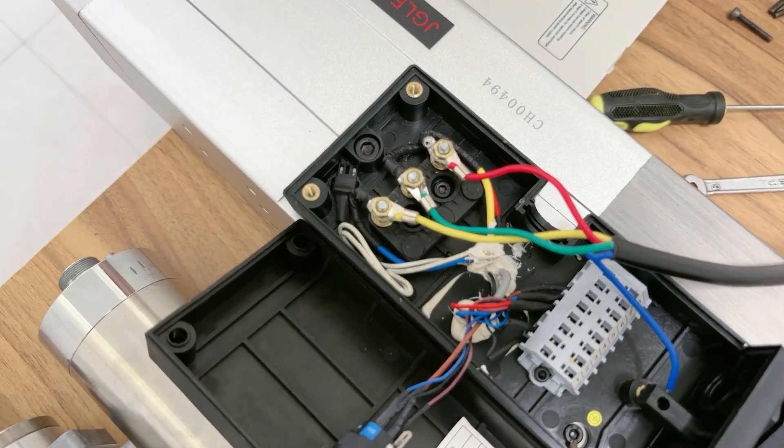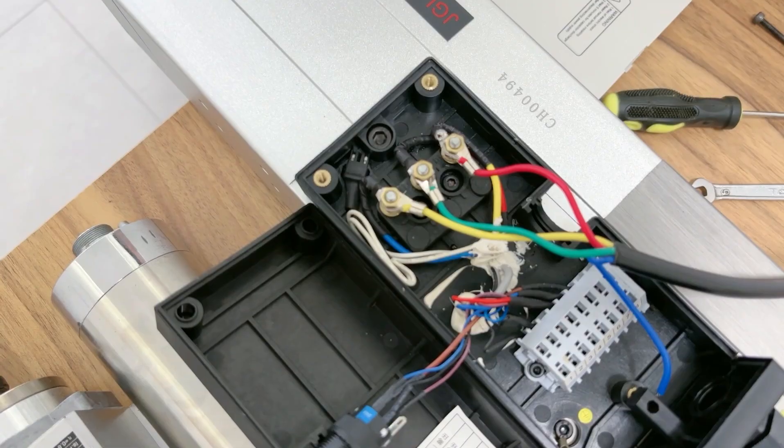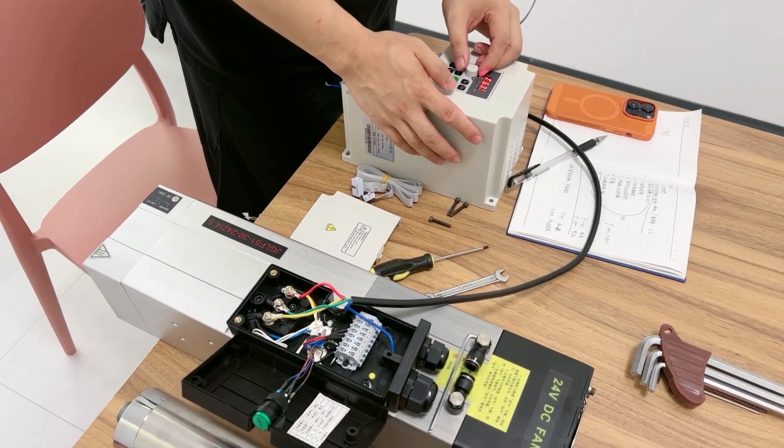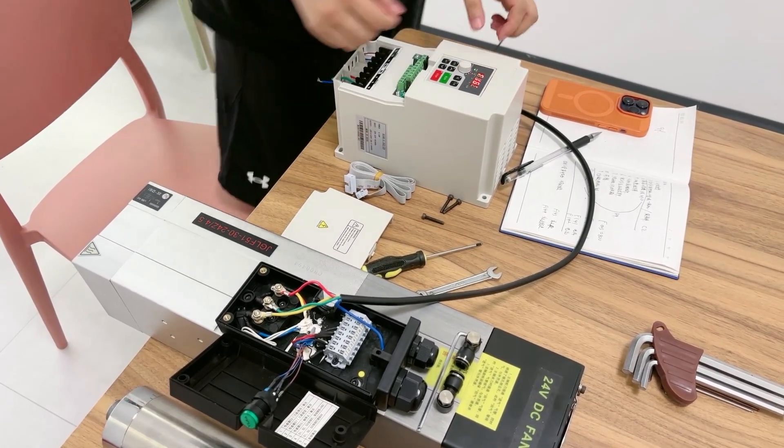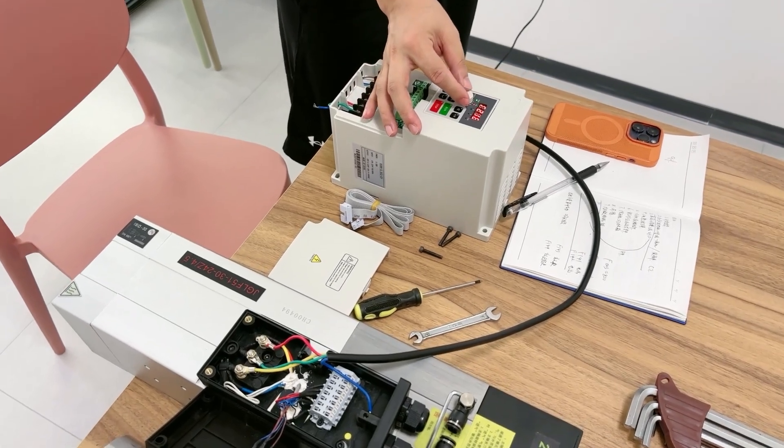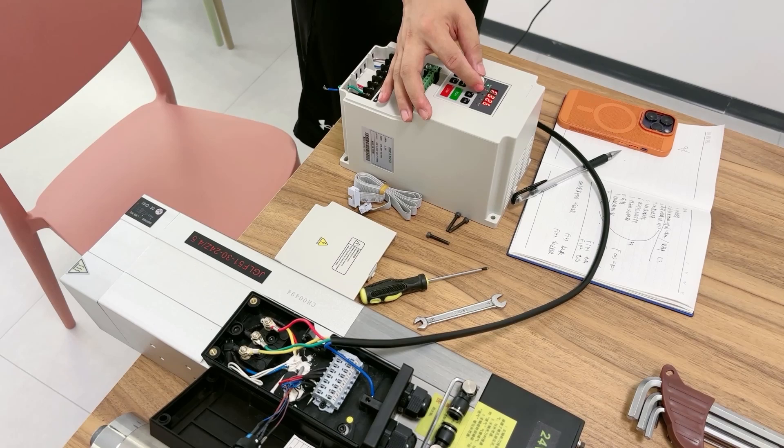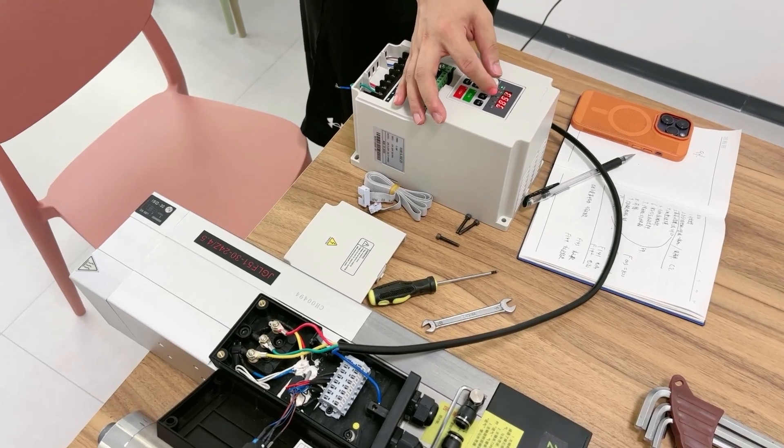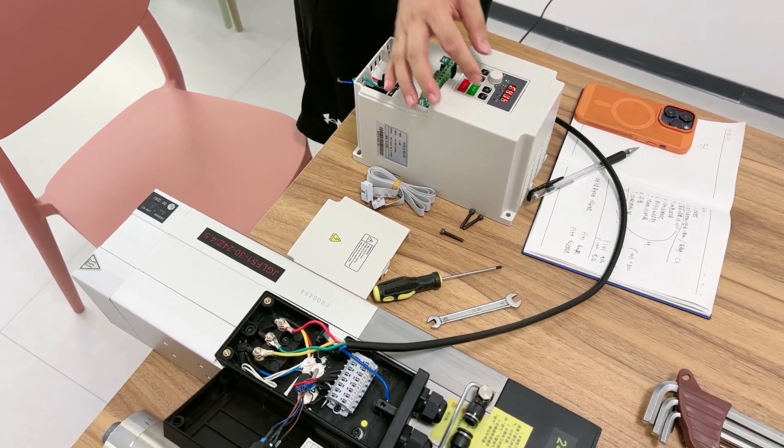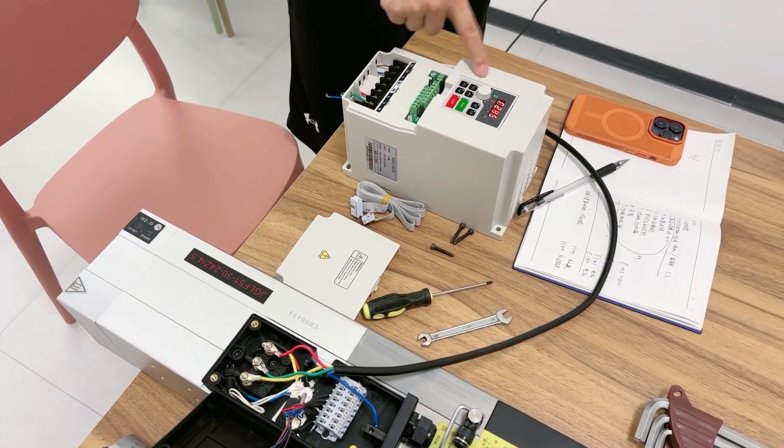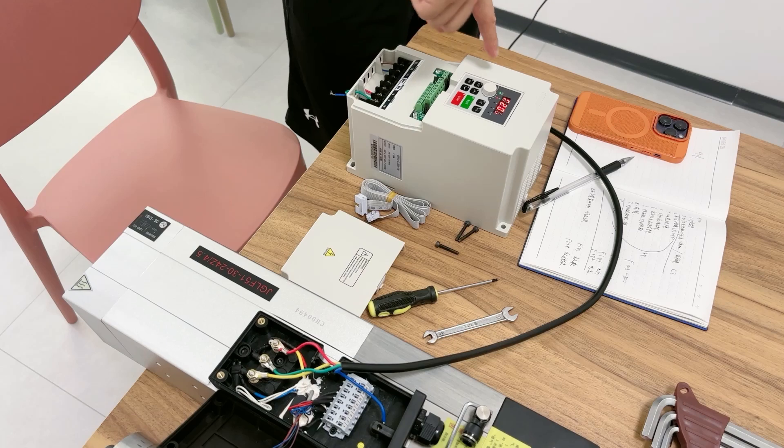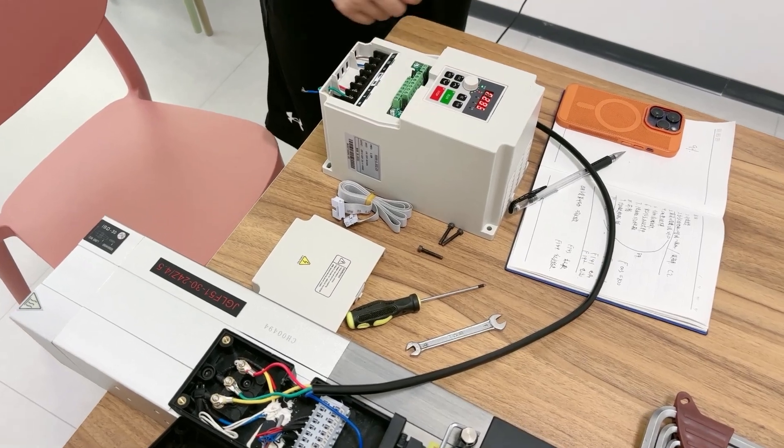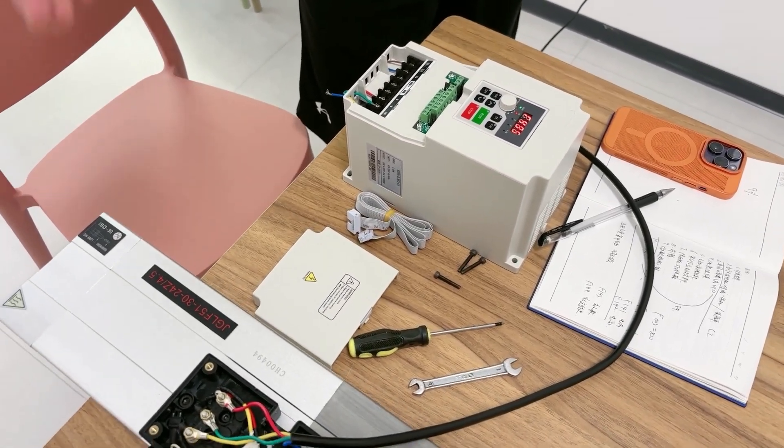Now from this button we can adjust the spindle speed when it's running. We just set the frequency parameter to 800, so when we adjust it to the end, it will show - look at that - the speed will rise one by one. Now it's 800 Hz and the speed is 24,000 RPM, very fast.